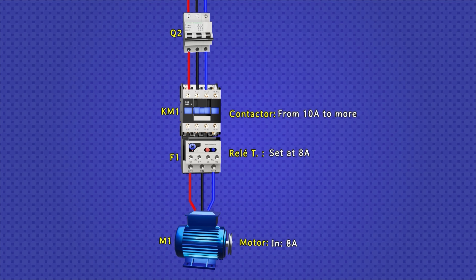Regarding the thermomagnetic switch, this is responsible for protecting the power cables. Therefore, its value has to be less than the current intensity that these cables can withstand. But it must also be taken into account that the cables have to withstand the maximum current intensity that can be set on the thermal relay. Here's another observation, which some of you may be wondering, and it is this. That both the thermal relay and the thermomagnetic switch protect against overload. And the difference between these is that the thermal relay is designed specifically for motors, while the thermomagnetic one is not, it is for a general case.